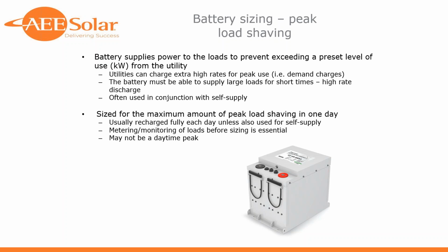Yeah, you have to really have a pretty good handle on what the demand charge loads are and arrange your system so that those can be mitigated with some energy storage. And it's often not for very long periods of time that you get these high power draws. So sometimes the battery has to be able to handle those extra fast and high levels of discharge. And it's also possible to do both self-supply, self-consumption, and do the demand charge mitigation with the same system. There are settings in a lot of the inverters that you can use to do both functions. Mm-hmm. But you do need to keep in mind that the battery may need to be capable of a little bit faster discharge sometimes for this.